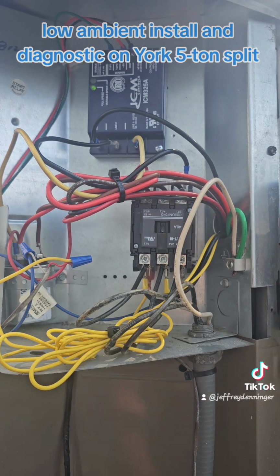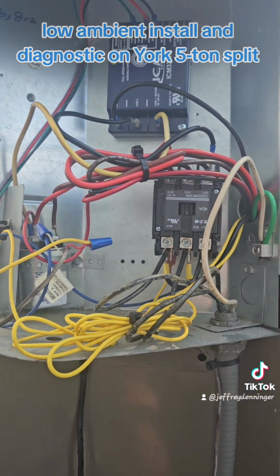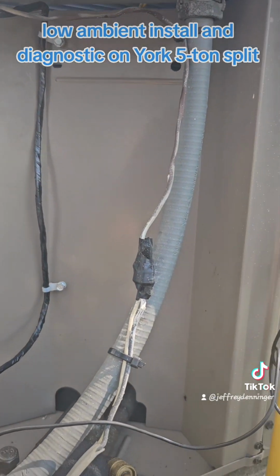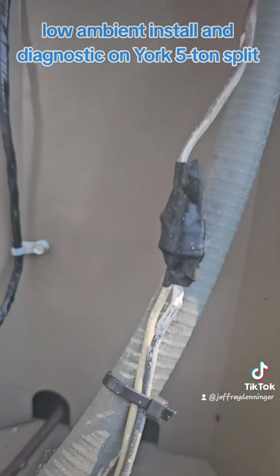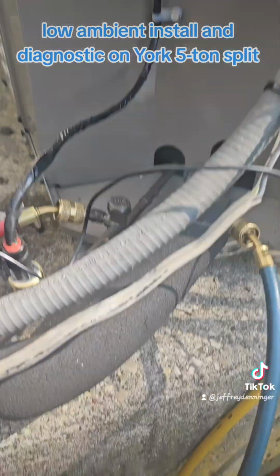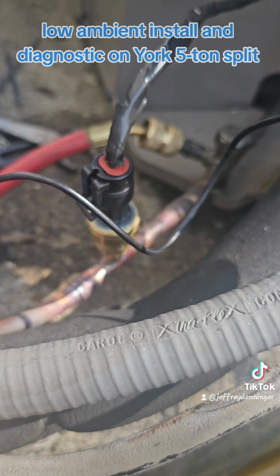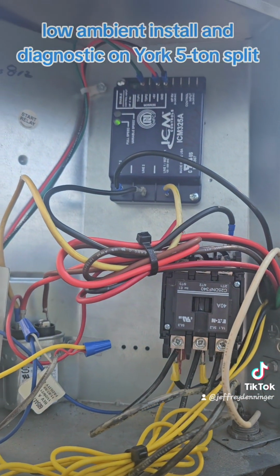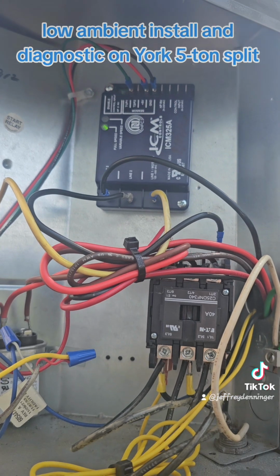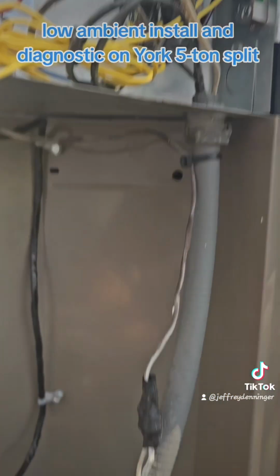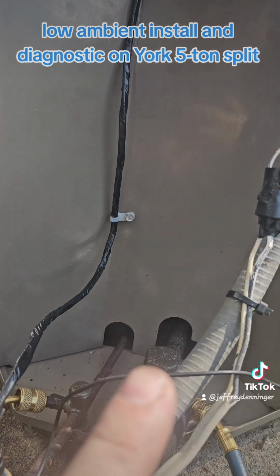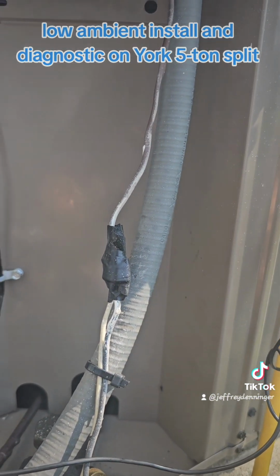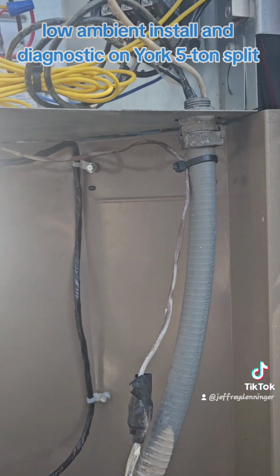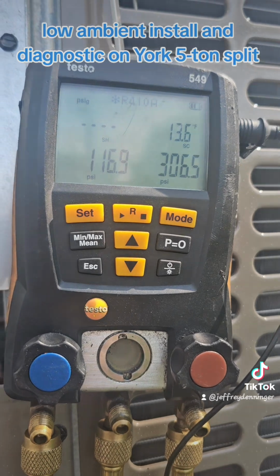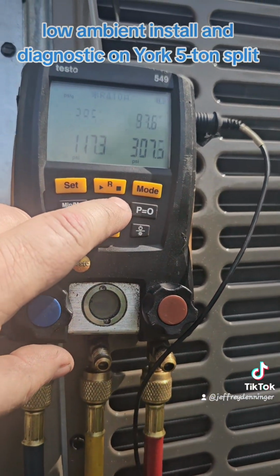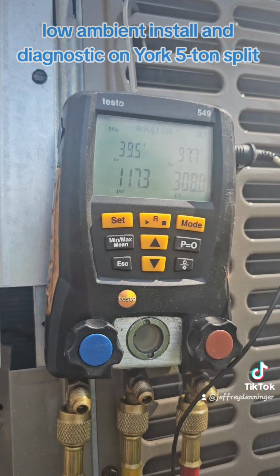Evacuate the system, flush it with nitrogen, make sure all the moisture and everything else was out. We put in a new dryer, which the dryer was partially plugged, causing part of our problem. We brazed in a new T so that we can do the pressure transducer for the low ambient. There's also a crankcase heater on the compressor inside. But right now, the unit is up and running. And the space is coming down.